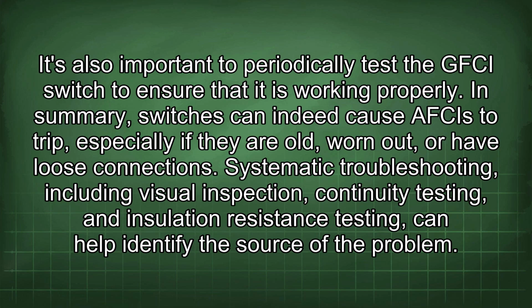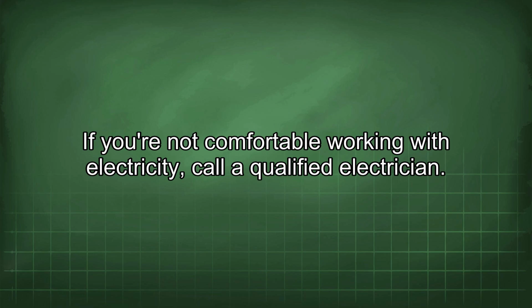In summary, switches can indeed cause an AFCI to trip, especially if they are old, worn out, or have loose connections. Systematic troubleshooting, including visual inspection, continuity testing, and insulation resistance testing, can help identify the source of the problem. If you're not comfortable working with electricity, call a qualified electrician.